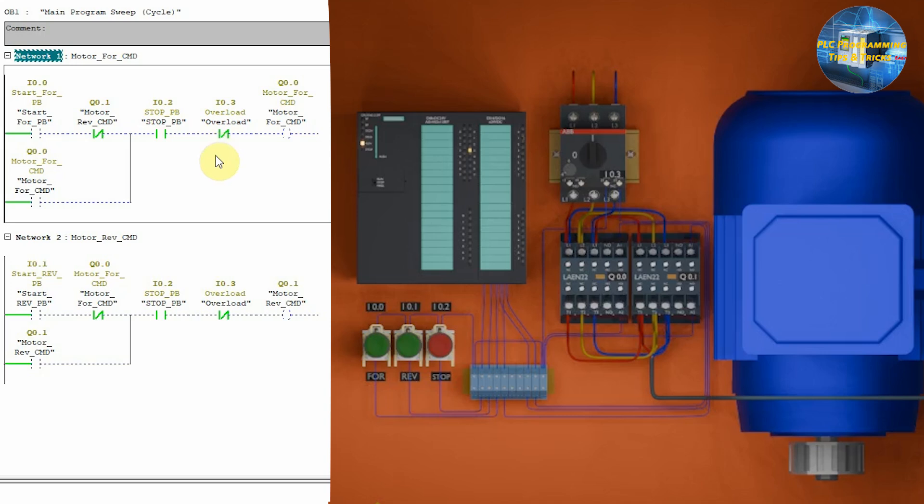This means that if somebody presses the stop push button I0.2, or the motor overloads and this overload contact I0.3 opens, this will latch off the motor forward start command Q0.0.